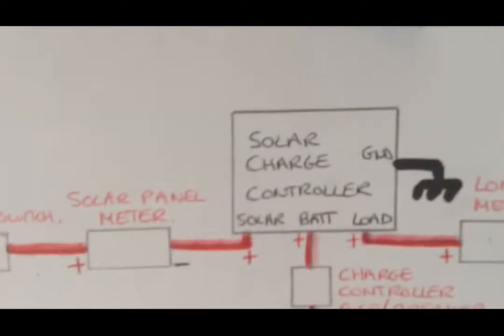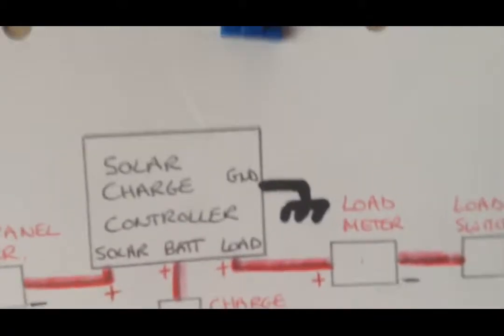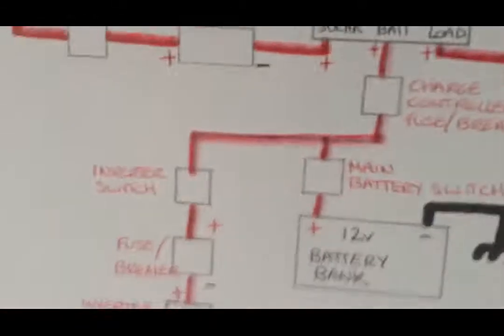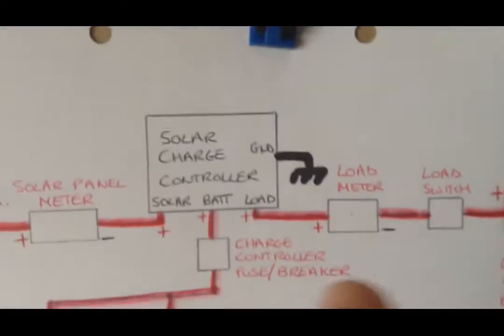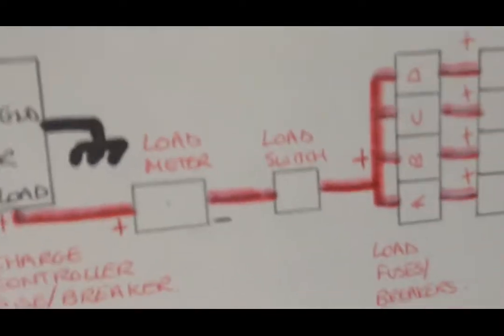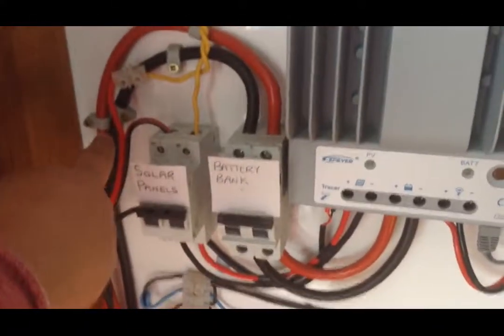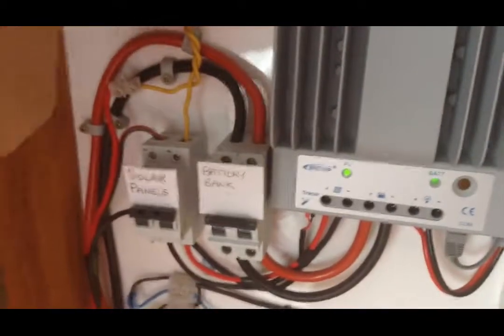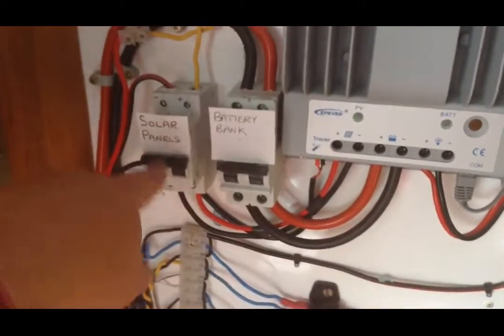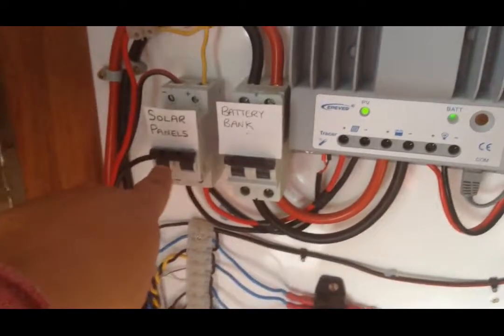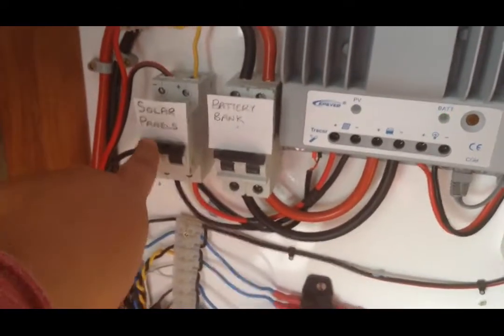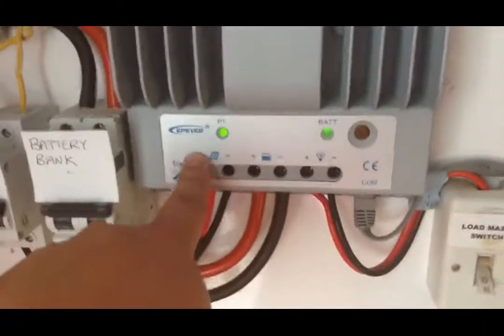So on this diagram here, I've only shown the positive wires, but obviously everything also has a ground wire. All the grounds are connected together. It just makes the diagram easier to see. So that's for the low voltage side of the system. So let me recap. We have solar panels coming in, goes through a meter, goes through a switch or breaker depending on what you have. A switch is the minimum that you need. Then we go to the input of the charge controller.